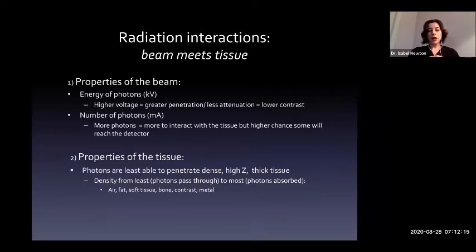So if you are looking at an area that is, let's say, the upper abdomen, and you're including part of the lung and you're not interested in the lung, it's important to remove that part, because then the automatic exposure control is averaging over a larger variety of tissues that may not be relevant. And so the contrast of your image is going to suffer, and you're going to have an incorrect number of photons being administered to achieve the same type of diagnostic image that you'd like to achieve.